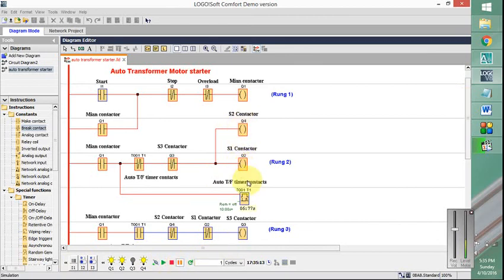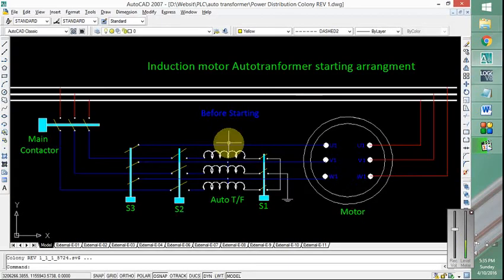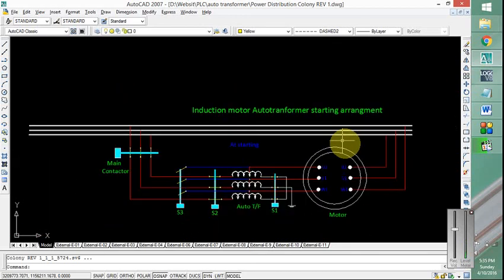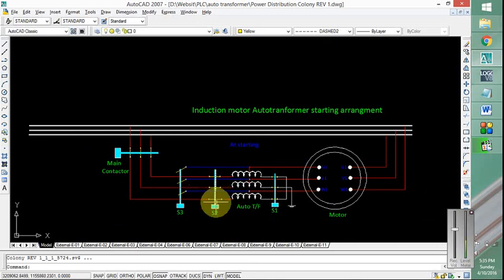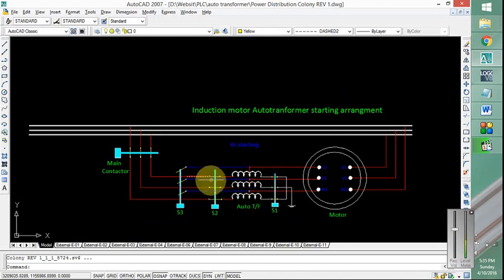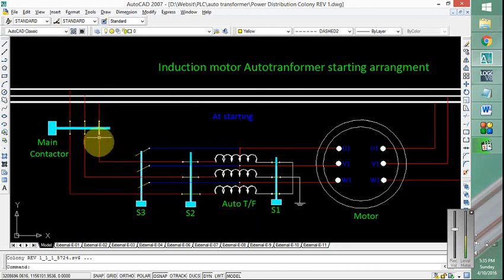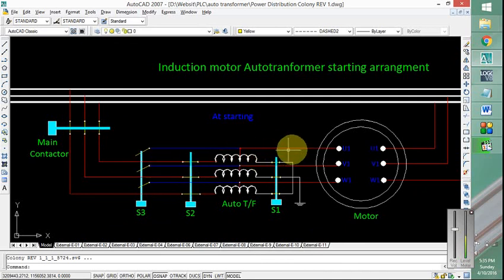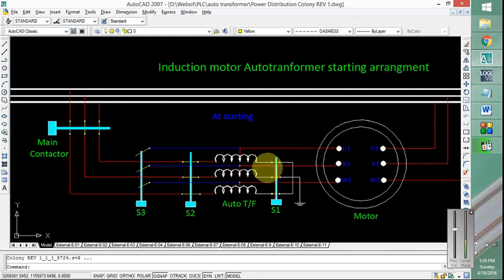And the timer has started its counting. I have just paused it. So in this time the current is flowing through auto transformer. Let us have a look. So when start button is pressed, as you can see this contactor is energized, and the switches are closed, S2 and S1. So the current comes from the main supply, goes through the auto transformer through its tapping into the motor, so reduced voltage is applied.